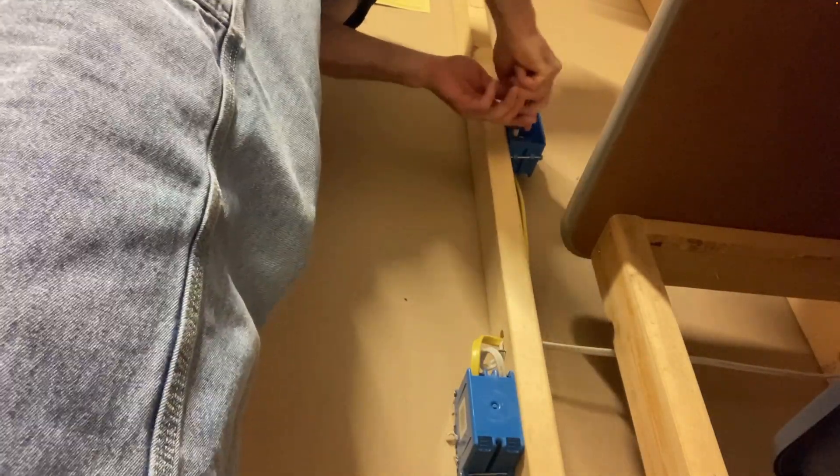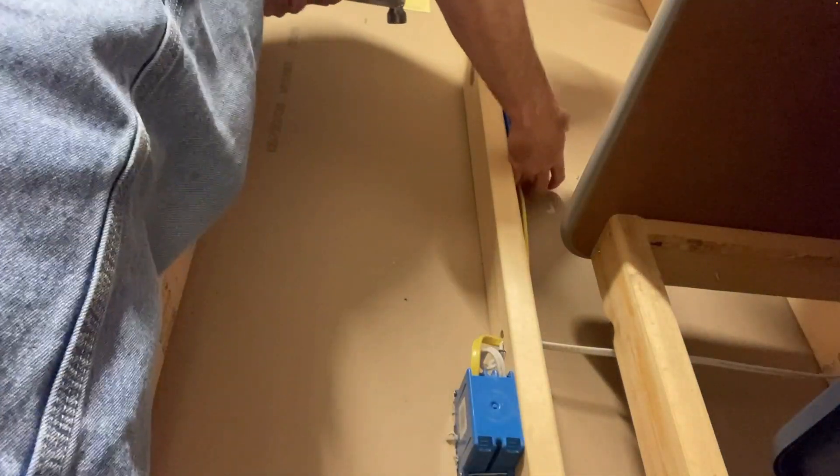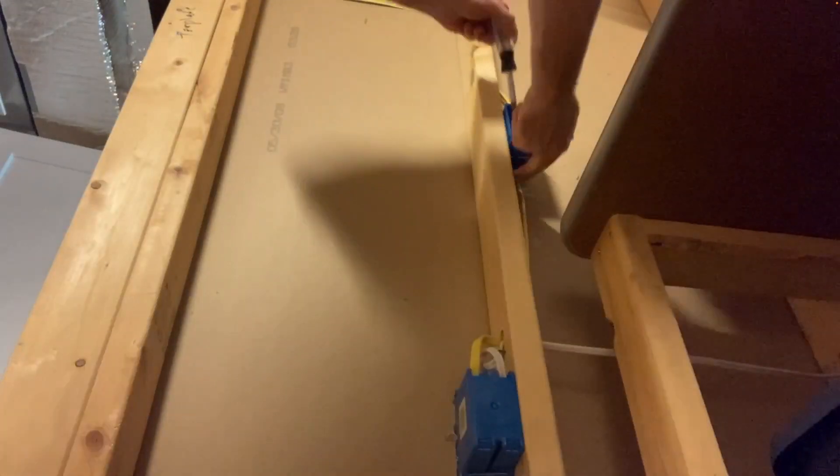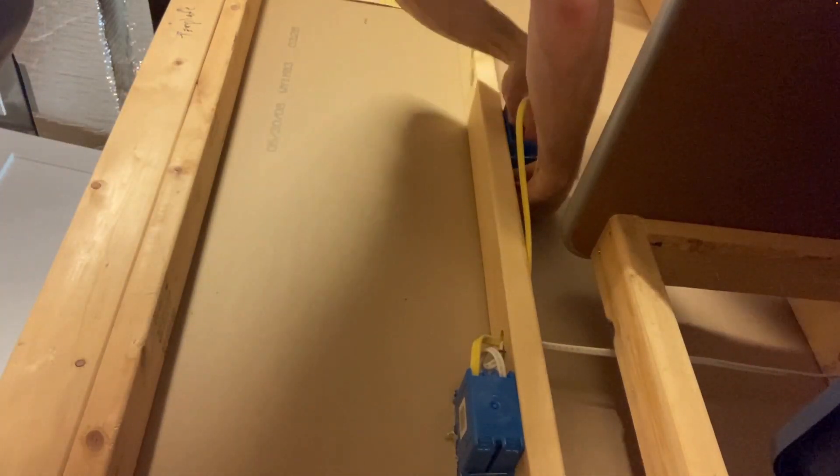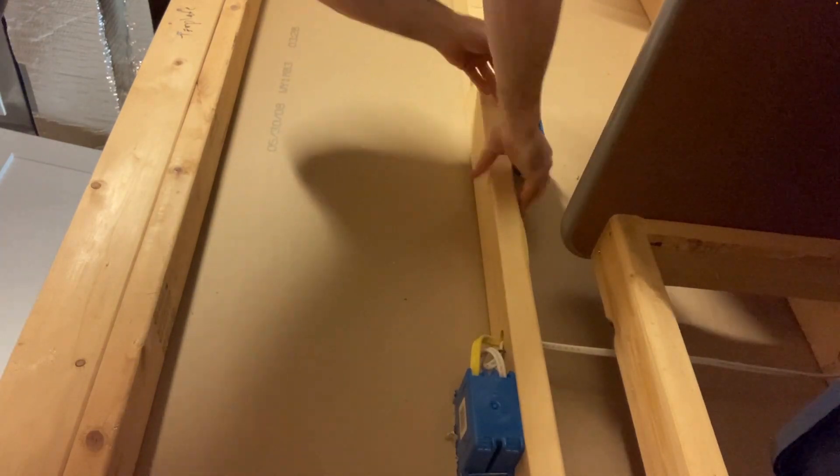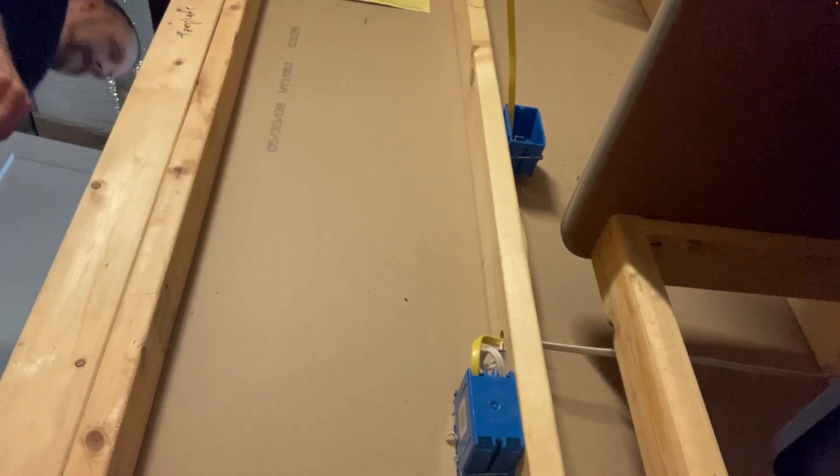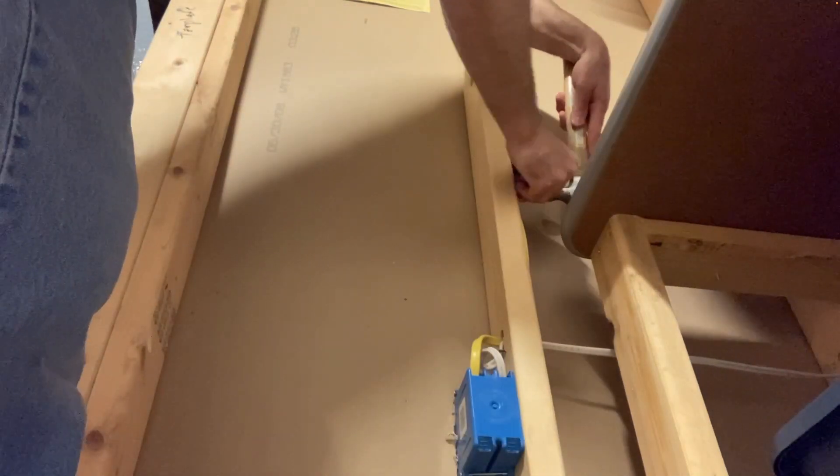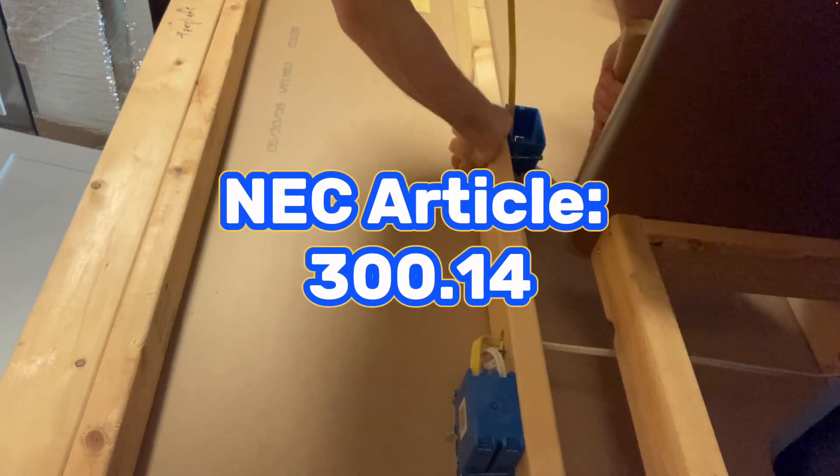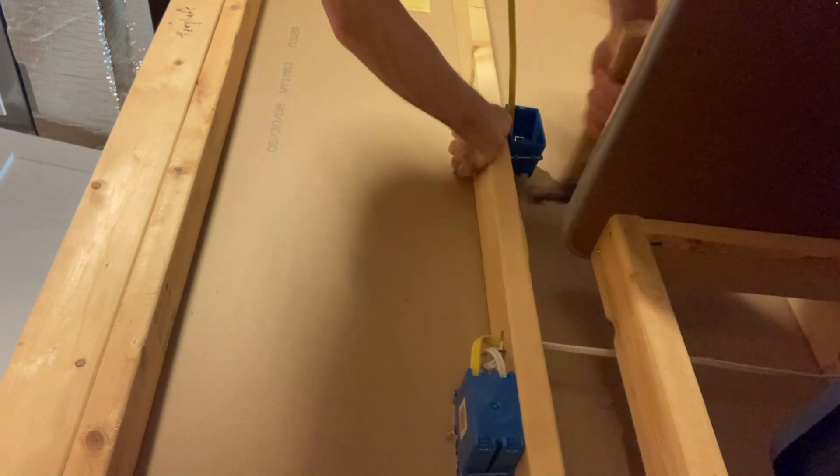I'm opening up the strain relief that grabs the Romex cable as you push it through the box. We'll feed our Romex through the new box. The NEC requires you want at least six inches of wire sticking out of the box to meet code.